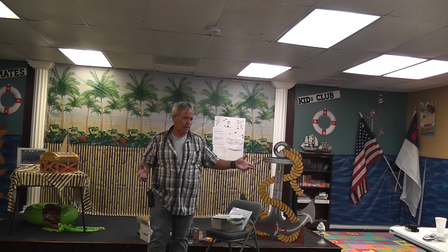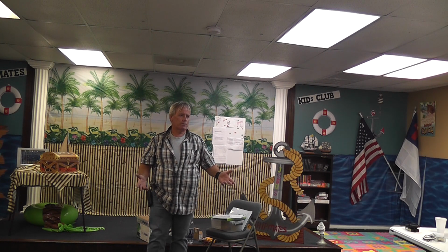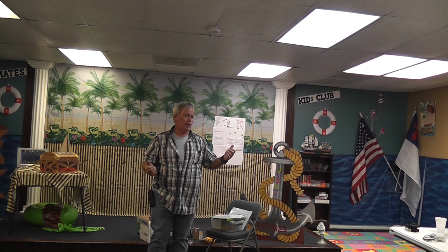What do you do when you put a Goodman in and you're under the length of the line set where you don't have to add new refrigerant? You open the valves and you start it up, right? Yeah. Nothing works right. Nothing. What's the problem? It's a brand new machine. Wound up pulling the whole charge, evacuating it, change the dryers, re-evacuate it. A brand new charge. It worked fine.